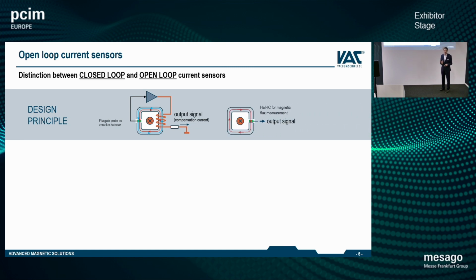If you contrast this now with an open-loop design, there you have a slightly different setup. We obviously again have a primary conductor that is generating a magnetic flux that is concentrated in the magnetic core. But now in the air gap, we directly have the Hall sensor, the Hall IC, for a direct magnetic flux detection in the air gap. Then the output signal is directly the measured magnetic flux and directly relates to the primary current.